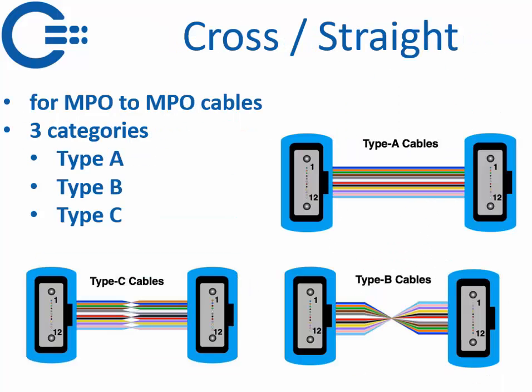Another important thing is the cross or straight configuration. For MPO there are three types of polarity: Type A, Type B, and Type C. Type A is straight — pin 1 is connected to pin 1. Type B is crossed — pin 1 is connected to pin 12. Type C is not really used much — it just swaps pairs 1-2 on each end. For QSFP to QSFP you always have to use Type B.